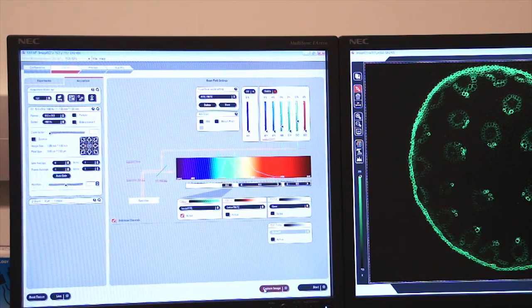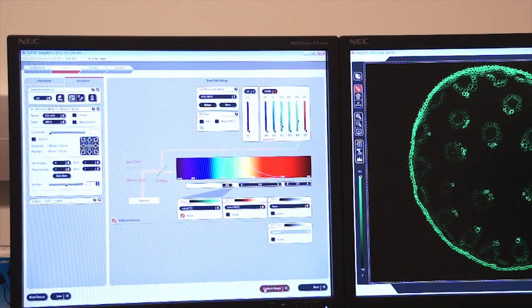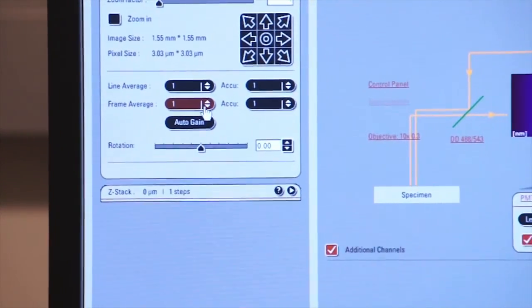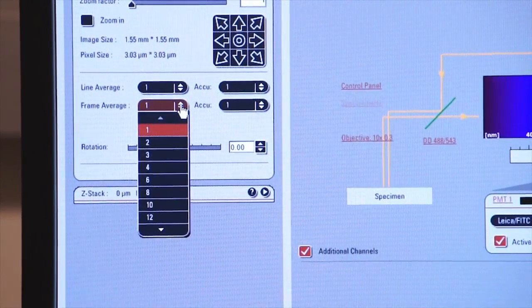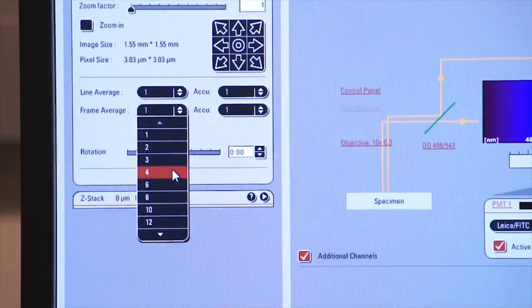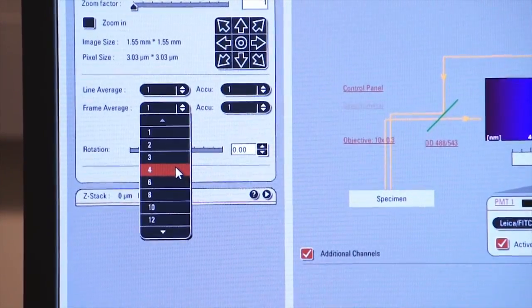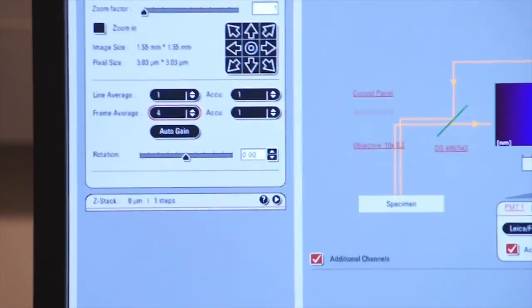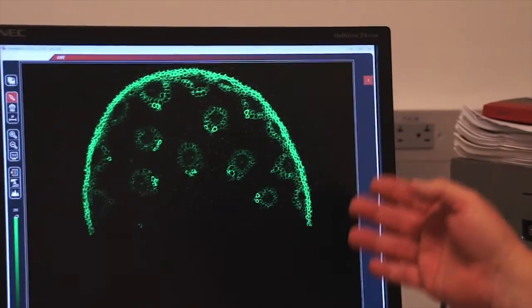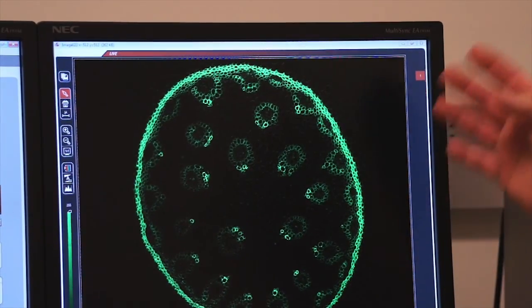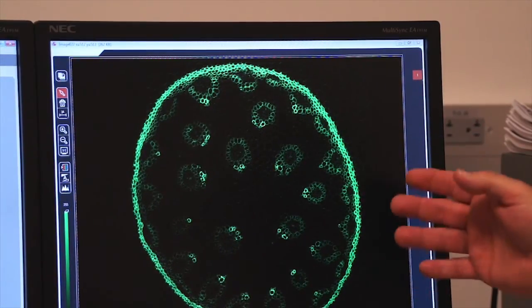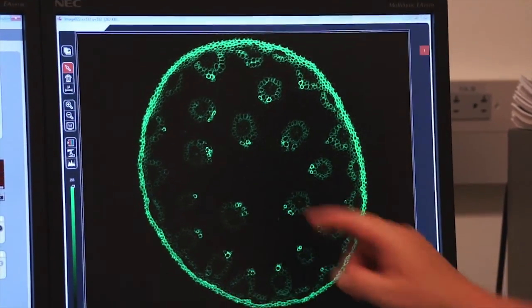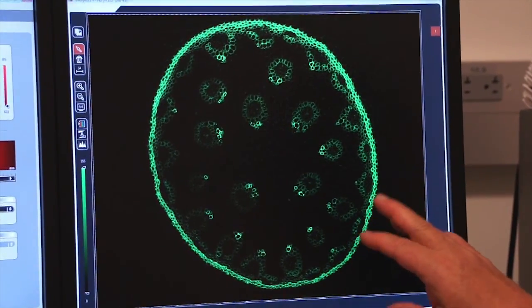Let's go back to line average and change that back to one. And now we'll try a frame average. You can also average the number of frames that you take per picture. So we'll do four frame averages. And if I click on capture image, I've told the system to take an image, but do four different frames. And you can see that took a little bit longer. And it is somewhat clearer, but line average tends to work a little bit better for sharpening up your image than does frame average.